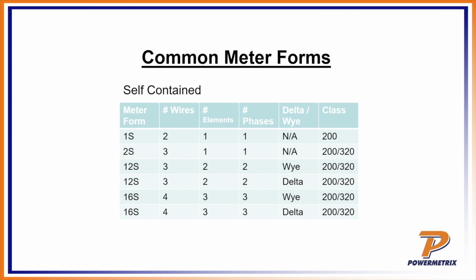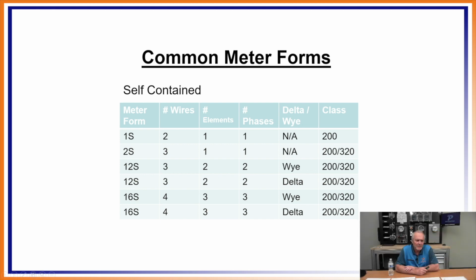Here we've got a little chart, if you ever want to use it, showing common meter forms. It shows first the self-contained: 1S, 2S, 12S, and 16S. On the 12S and the 16S we're showing both the Ys and the deltas, because you can have a Y or a delta with a 12 or a 16. And notice over on the far right, the class. That's your current class, right? So that tells us what current they can handle.